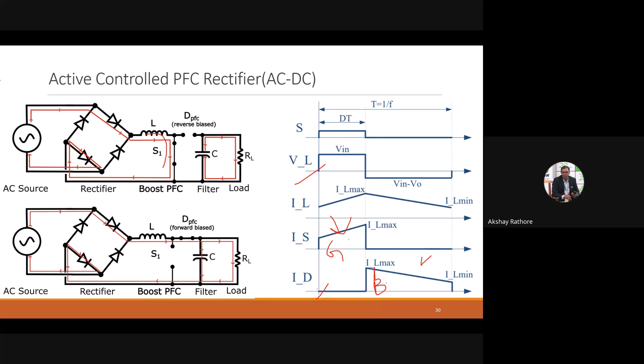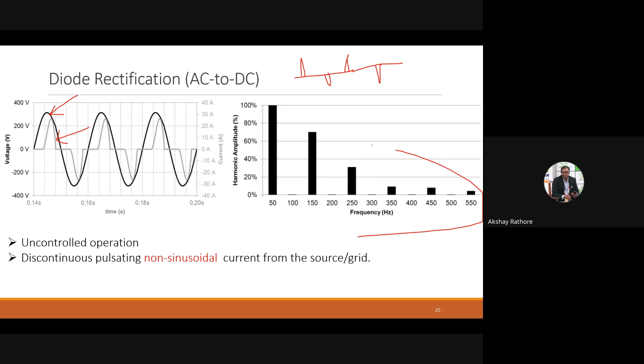When we put in an LC filter, which is a low pass filter, the filter requirements become much less for high frequency. Then you get a sinusoidal waveform with quite low distortion. Earlier, with the diode-based system, the distortion was quite high, and that was low frequency harmonic, so the filter size was quite large. But here we have high frequency harmonics — low frequency harmonics are not present, so the filter size becomes very small.